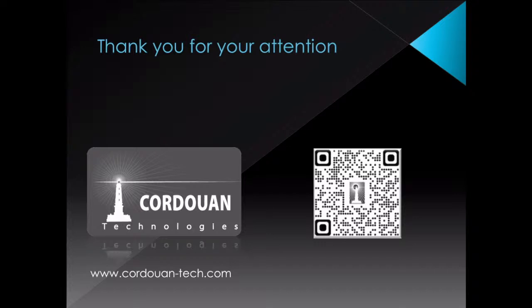Usually, for absorbing nanoparticles, we change the wavelength of the laser a little bit in order to be outside of the absorption band of the nanoparticles. For example, for quantum dots, particles with a rare earth inside, and very small. We are able to measure them by shifting the laser wavelength, and we even have an application note that we can send you if you want to see it.